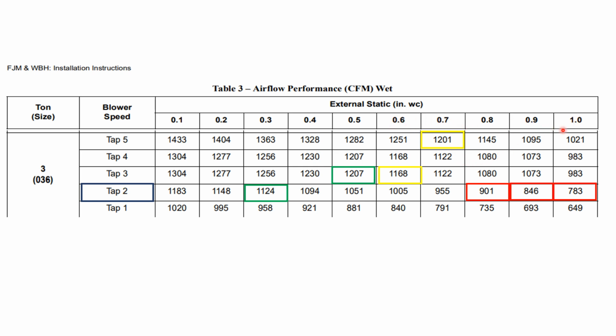Anything over here was damaging the equipment, which means that in two to four years, your compressor would go out because of excess pressure pushing back into the compressor, or you would pop a coil, or your X13 blower motor would go out.